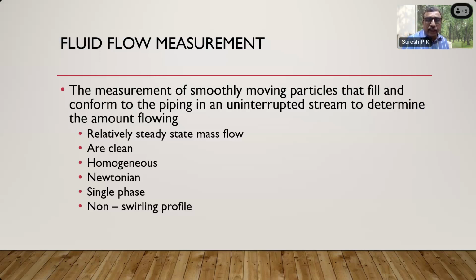So it is not good for the measuring instrument also, because all measuring instruments are designed for certain velocities. Air velocity is always high. So if you try to pass air through the water meter, it can get damaged. Vice versa is also true. Like a gas meter, if water or liquid particles enter the gas, it can damage the meter, and the measurement accuracy will go.